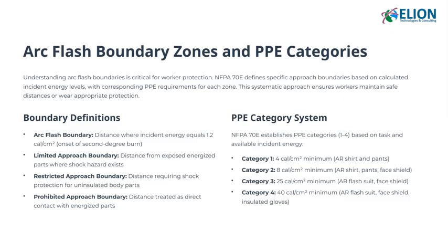Let's delve into the arc flash boundary zones and PPE categories, which are essential for worker safety. Understanding these boundaries helps ensure that workers maintain safe distances or wear the appropriate protective equipment based on the potential incident energy. First, the arc flash boundary is the distance from the energized equipment where the incident energy reaches 1.2 calories per square centimeter. This is the point where second-degree burns could occur, so staying outside this boundary or wearing proper PPE is critical.